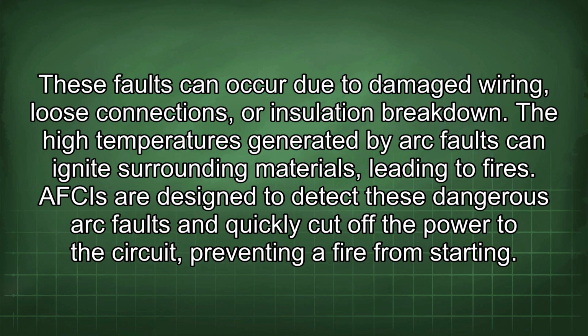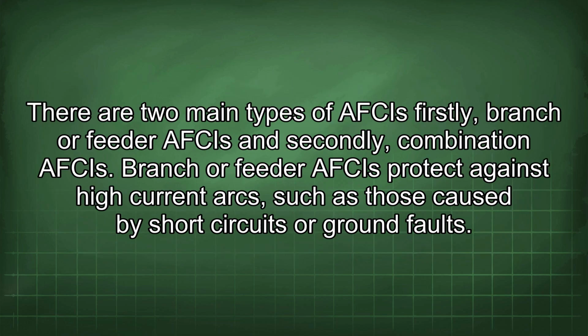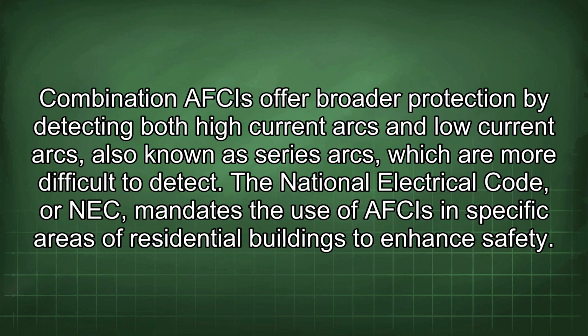AFCIs are designed to detect these dangerous arc faults and quickly cut off the power to the circuit, preventing a fire from starting. There are two main types of AFCIs: firstly, branch or feeder AFCIs, and secondly, combination AFCIs. Branch or feeder AFCIs protect against high current arcs, such as those caused by short circuits or ground faults. Combination AFCIs offer broader protection by detecting both high current arcs and low current arcs, also known as series arcs, which are more difficult to detect.